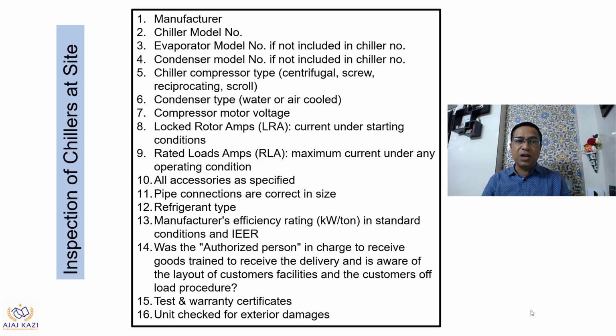Within the chiller model, we have the evaporator model and then the condenser model. Those also need to be checked. Most of the time during production there can be a mismatch, maybe a wrong evaporator is attached. Generally it doesn't happen, but it can happen. So it is our duty to check the chiller model number, then its evaporator model number, condenser model number, and obviously the compressors. Which type of compressors? The compressor model and compressor type need to be checked.